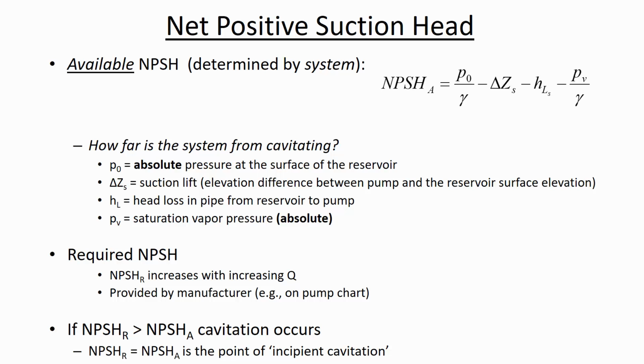And so sometimes you'll be asked the question, for example, how high above the water surface can you place the pump? In a situation like that, you'd set the required suction head equal to the available suction head, and then solve for this delta Z to find out how high the pump could be. Or maybe somebody would be interested in how long the suction side pump segment, the pipe, can be. The head losses on the suction side pipe are going to be reducing the amount of available head.